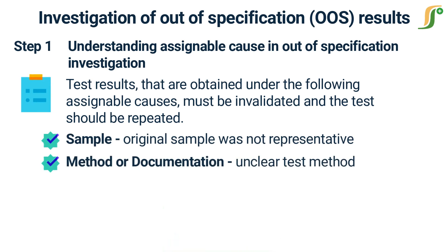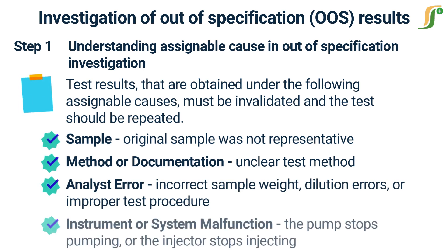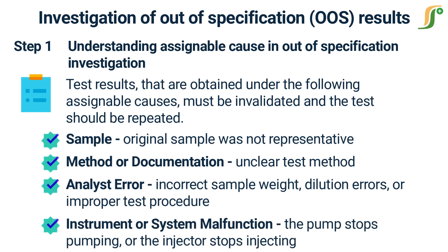Second: unclear test method or standard operating procedure directions which resulted in incorrect test execution. Third, analyst error — examples include but are not restricted to the incorrect weight of the sample used, sample or sample solution spills, dilution errors, or improper test procedure. Fourth, instrument or system malfunction — examples include but are not restricted to interfering electrical surges or spikes, the pump stops pumping, or the injector stops injecting.